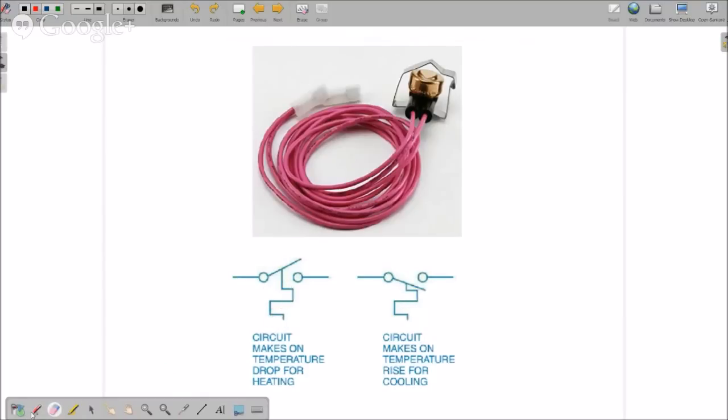No matter what type of switch it is, this symbol indicates a temperature controlled switch. And again, this shows the normal, whenever you see them, they're in their normal position. And you just need to know what the temperature is that these make and break at. So you can determine physically what's happening because the schematic diagram, again, just shows it in its normal position.